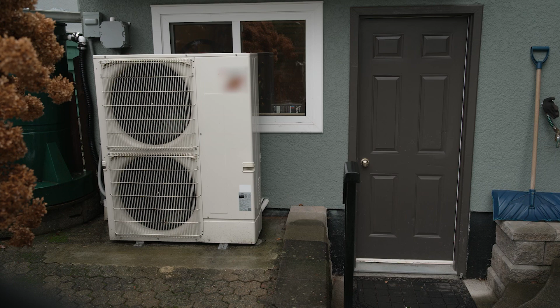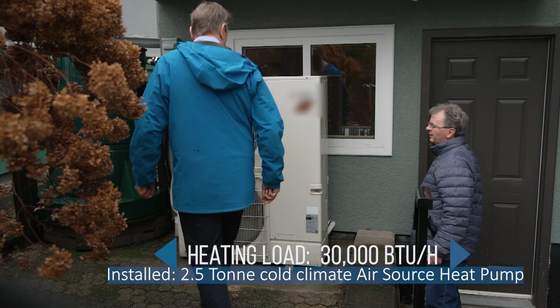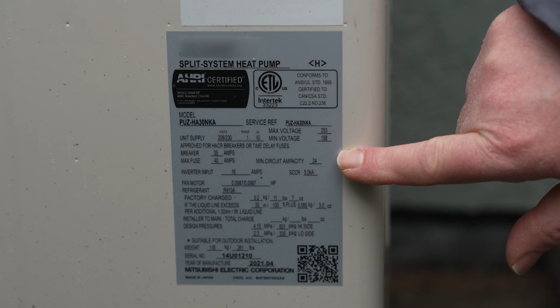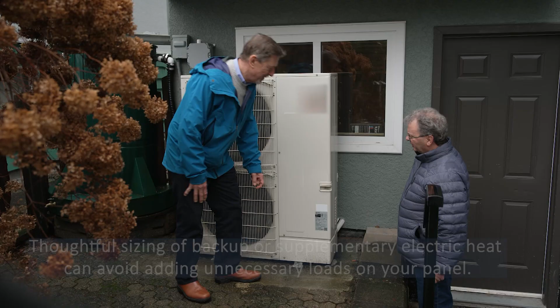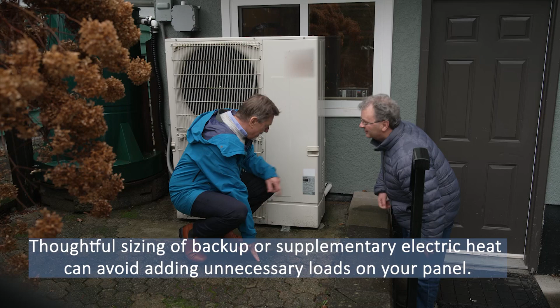Our energy advisor told us our heat load was around 30,000 BTUs per hour. We selected a 2.5 ton cold climate heat pump that meets the full heating capacity of our home at design conditions when the outside temperature's at -8. Some contractors default to putting in electric resistance heaters that meet the full heating load of the home. This adds significant load to the panel capacity requirements and is probably overkill. You may opt for a smaller electric heater that's adequate to supplement the heat pump but minimizes the load on the panel. Gary's 2.5 ton heat pump system has a maximum rated capacity of 34 amps, and it required a 40 amp breaker. We felt that was possibly doable on Gary's 100 amp service.